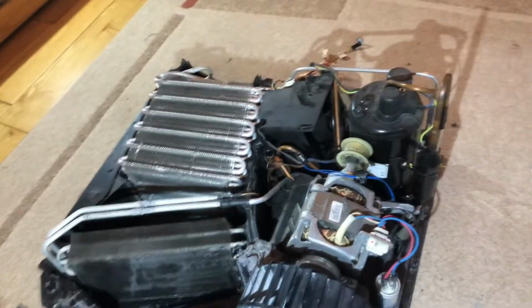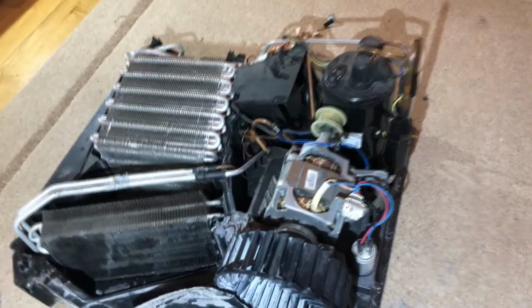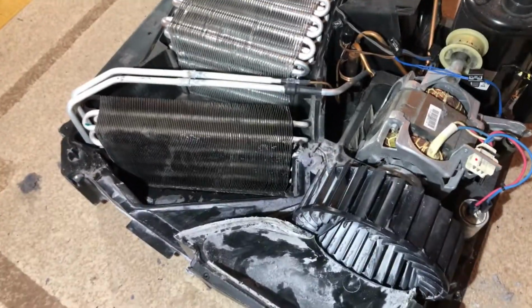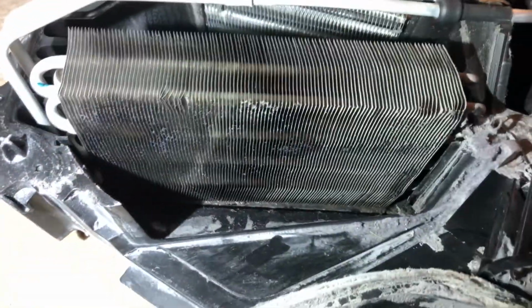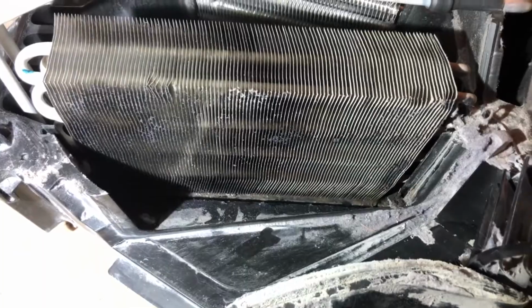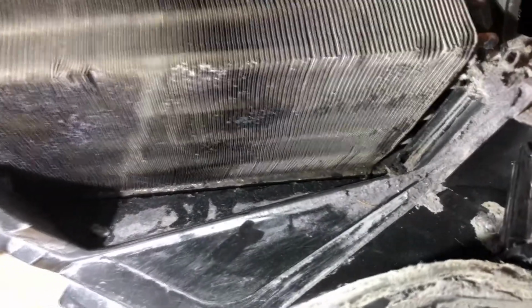A filter was in an unbearable condition. As you'll see here, this heat exchanger was full of dust. I have to take it out and jet wash it - very slowly, not a very powerful jet, because you will bend the fins and then the air will not circulate.